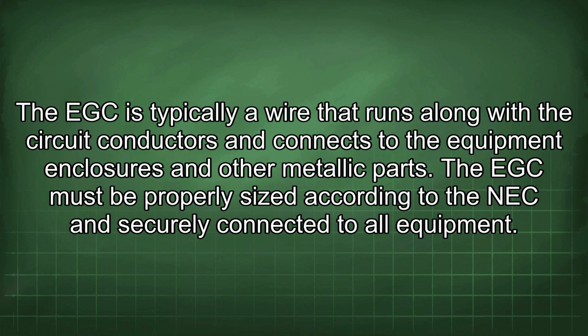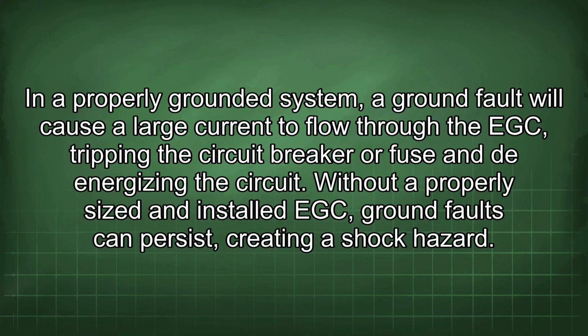The EGC must be properly sized according to the NEC and securely connected to all equipment. In a properly grounded system, a ground fault will cause a large current to flow through the EGC, tripping the circuit breaker or fuse and de-energizing the circuit. Without a properly sized and installed EGC, ground faults can persist, creating a shock hazard.